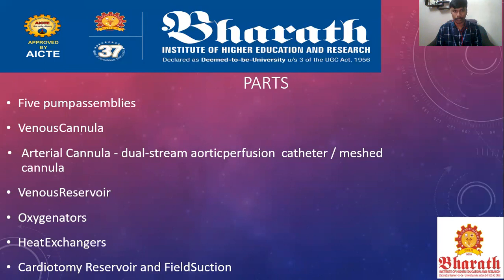The venous reservoir will act as storage for the blood until the deoxygenated blood is converted into oxygenated blood. Blood will be stored there. An oxygenator is used for oxygenation, for purification of blood, to make the blood oxygenated. We will be using oxygenators for embedding the O2 molecules inside the blood, and heat exchangers to maintain the temperature parameters of the blood externally. And the cardiotomy reservoir and field suction will be used as the setup for regulating this blood flow and this purification process without any error or delay. These are the parts that will be functioning accordingly for this purification process.